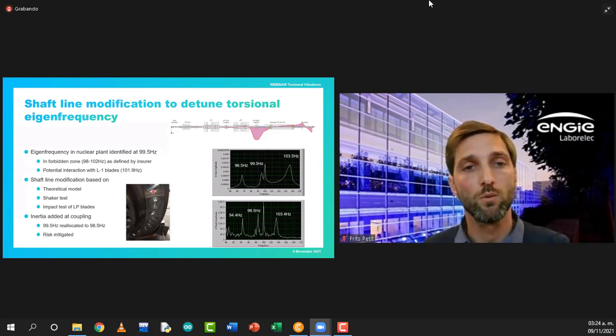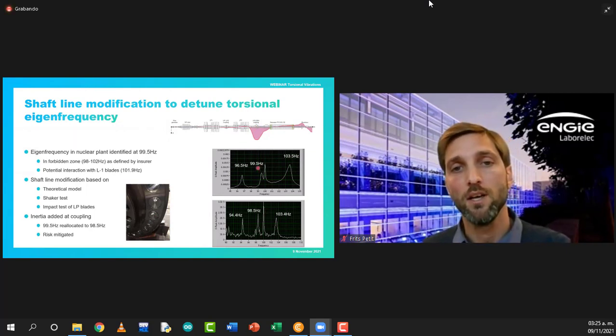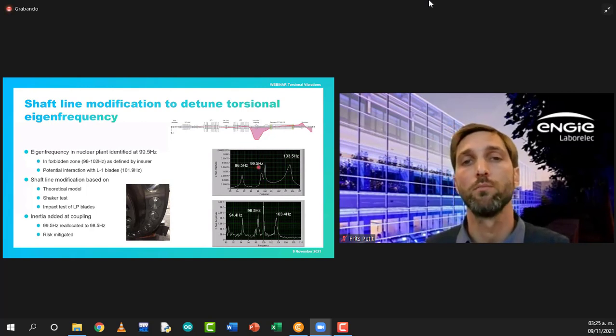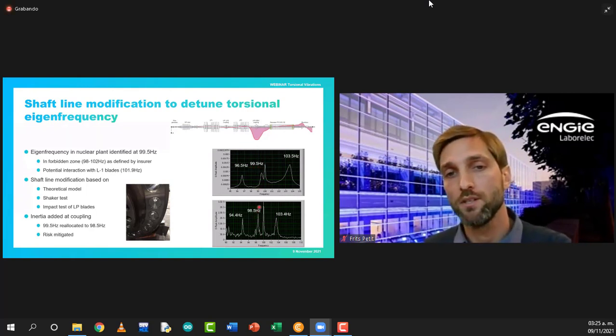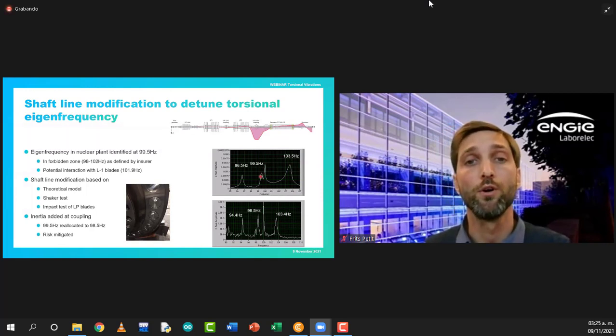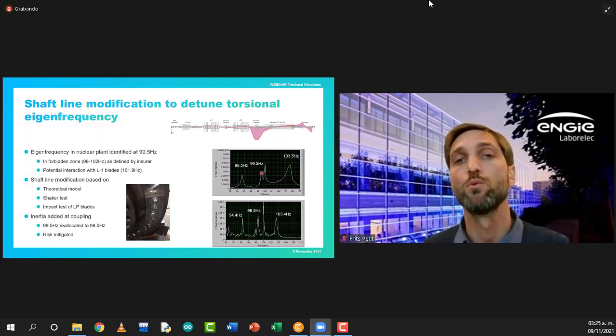And so in the end what we did is we added inertia at the coupling here between the LP turbine and the generator, which then reallocated the natural frequency from 99.5 to 98.5. You might say this is only 1 Hertz, but 1 Hertz in torsional vibration is really a lot, and this was actually sufficient to mitigate the risk.